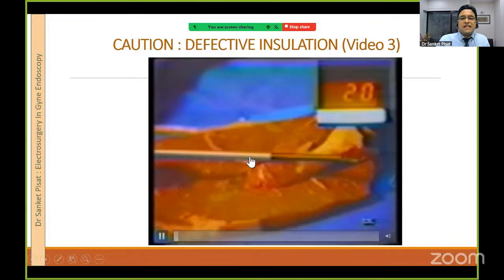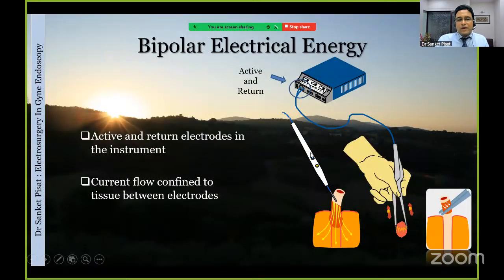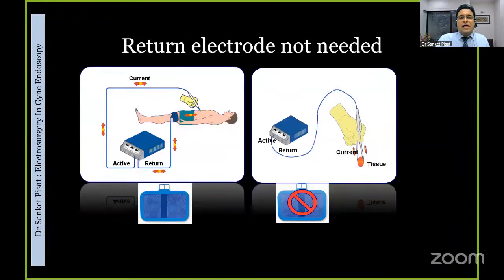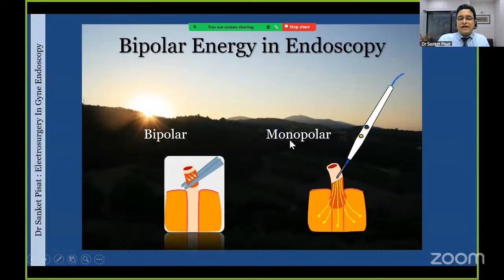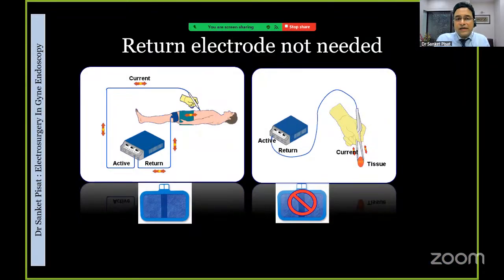Then moving on from monopolar to bipolar energy, a much safer form of energy. In a sense, monopolar is also very safe, but this is safe in the sense that the active and return electrodes are in the same instrument, and hence current flow is confined to the tissue between the two electrodes. Because current flows directly from one prong of the bipolar instrument to the other prong, a return electrode is not needed in bipolar. Effectively, if you are going to use only bipolar energy, then you do not require a patient electrode return plate.